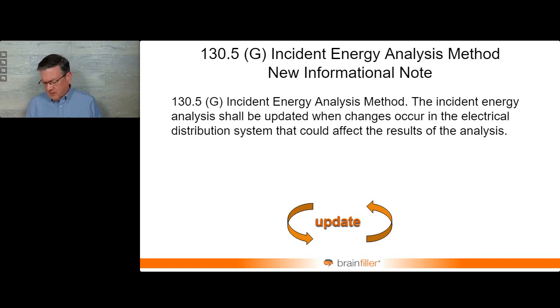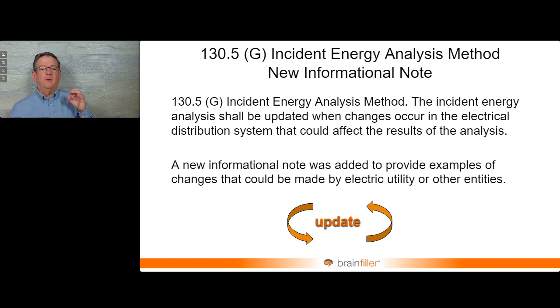There was another clarification that was made: NFPA 70E says you're supposed to go back and review the incident energy analysis at intervals not to exceed 5 years, or if significant changes have occurred that could affect the results of the analysis. And people think, well, what could that be? What kind of changes are we talking about? Well, there could be a lot of things that could change the incident energy.